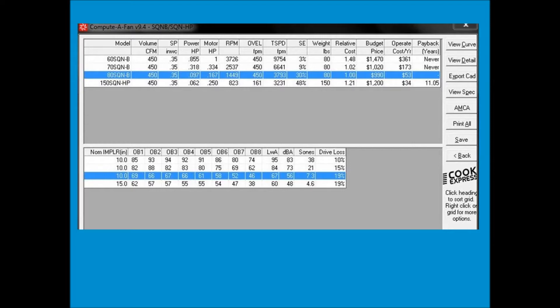For example, here is a selection — whether it's the catalog data or the software selection program, it shows you what size fans can do the performance at a stable spot on the fan curve. But not all selections are the same and not all selections are good selections. Look at this one here. The first one it shows is a size 60, the 60 SQNB in the square inline fan. That fan can do the performance of 450 CFM at 0.35 inches of pressure, but it needs to run at 3,700 RPM.